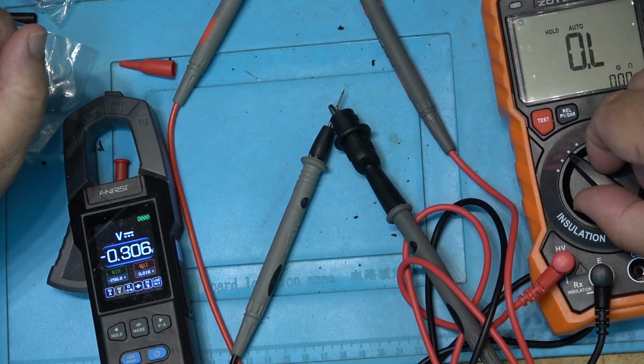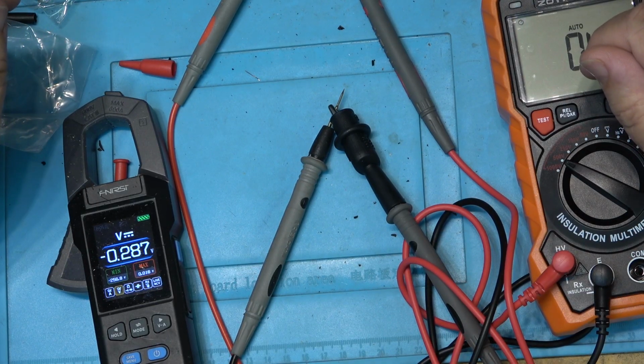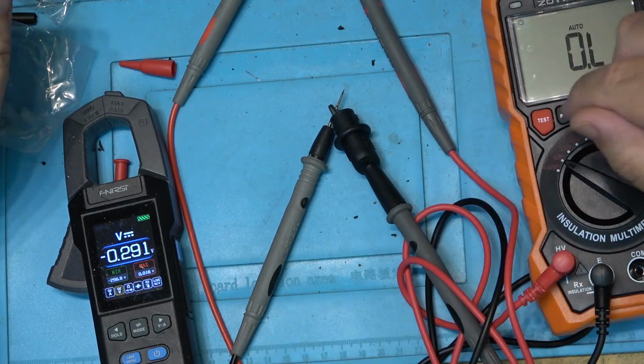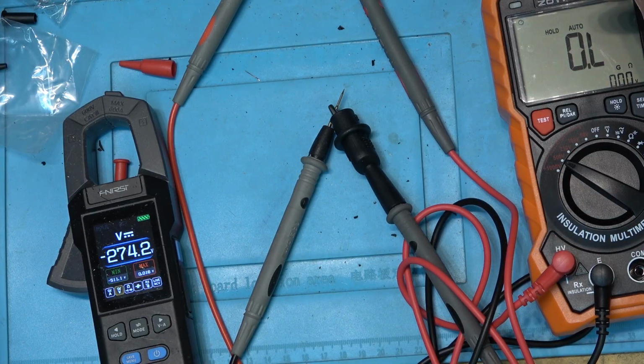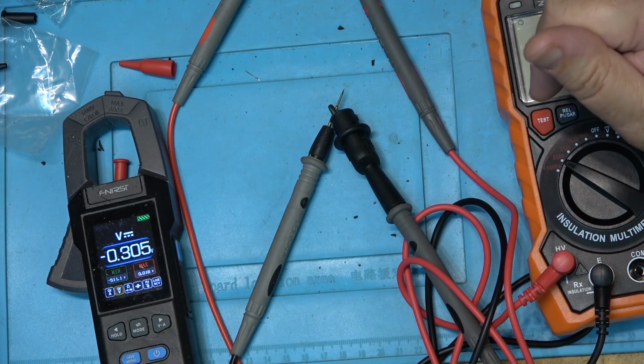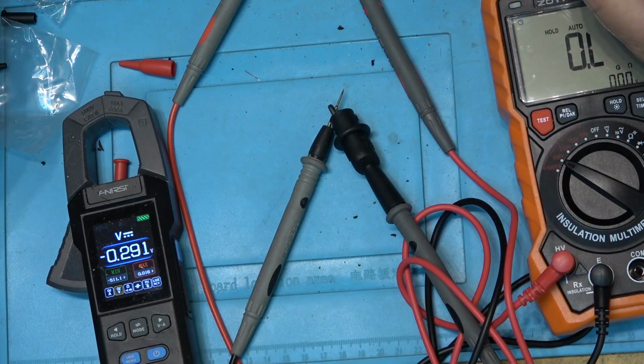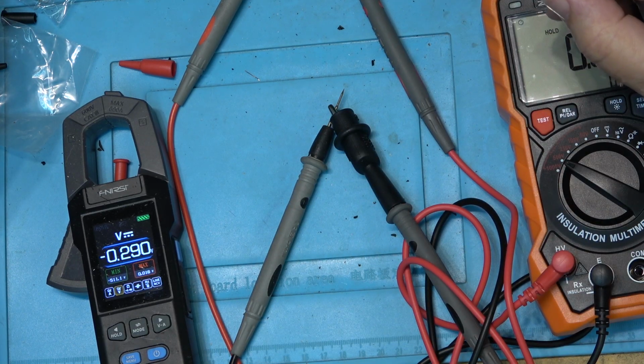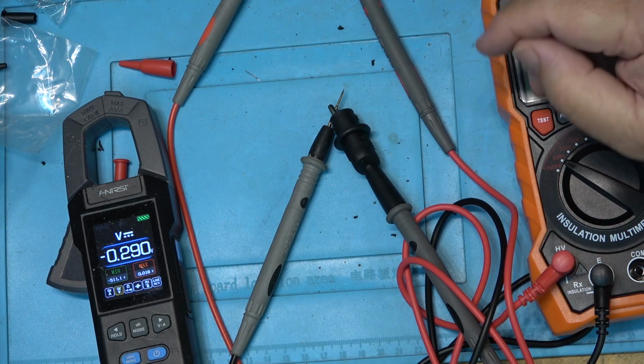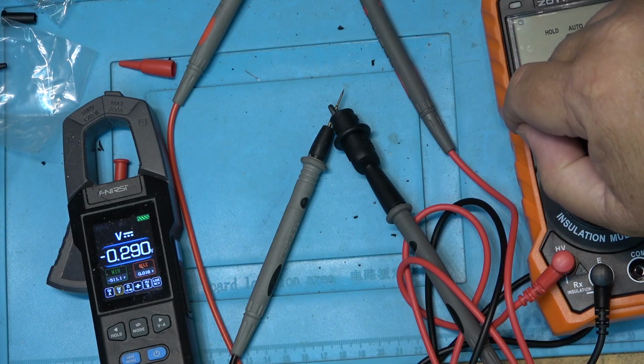I could put this on peak mode. We'll test it to 500. I'm not going to go to 1,000 on here, but I'll do 500. 500 there. See, it generates a pulse. And I guess I could go to 1,000 if I really wanted. This meter says it will handle 1,000 volts, but I'm not going to take it to 1,000. I'm only going to take it to 500. That's how these resistance or breakdown meters will test.